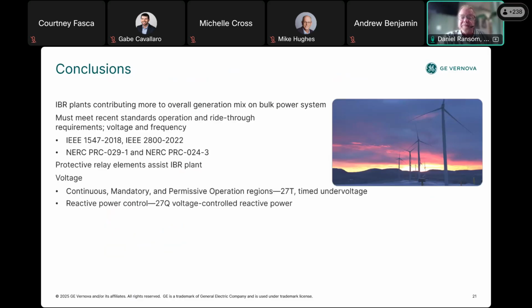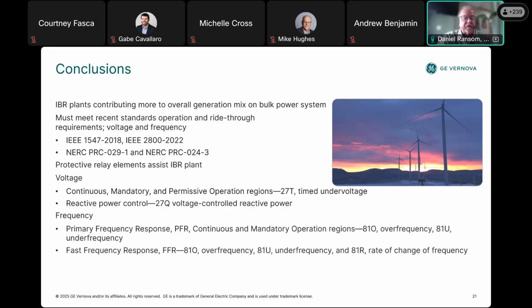I've shown you a time-qualified phase undervoltage element that exists at the point of metering, the reference point of applicability, and it signals the IBR plant to perform mandatory operation so that we can prevent grid collapse. The standards, national grid codes, and regulations require not only voltage protection, but frequency ride-through protection as well. And you can see those in the 81O and U elements and the 81R rate of change of frequency elements.